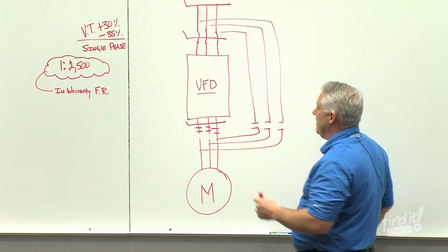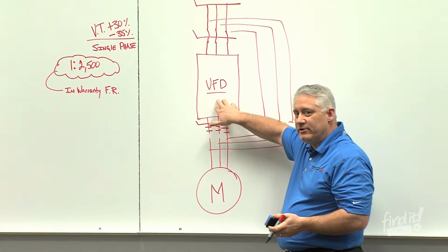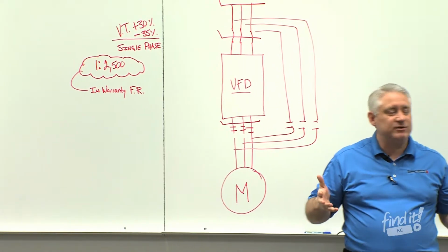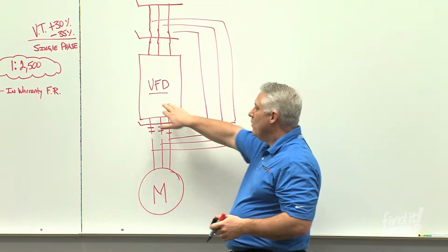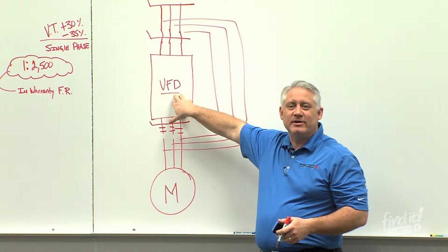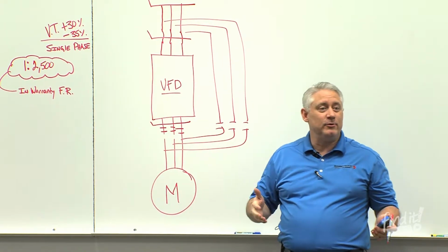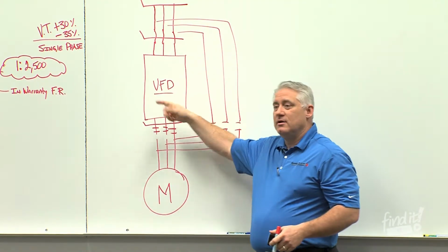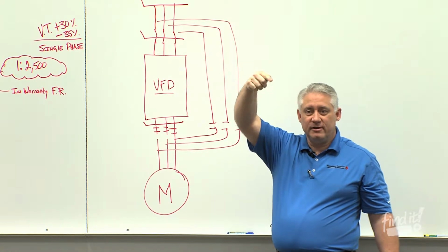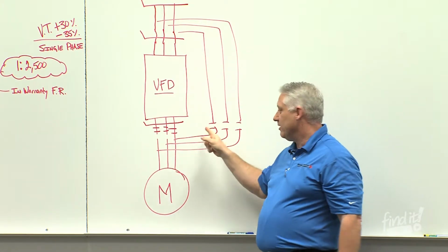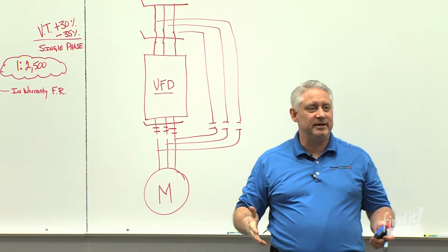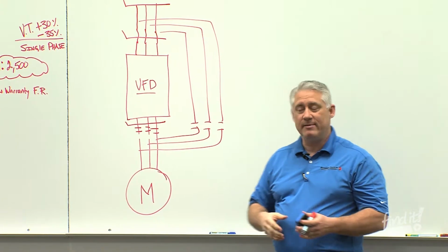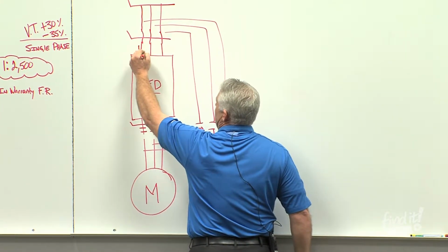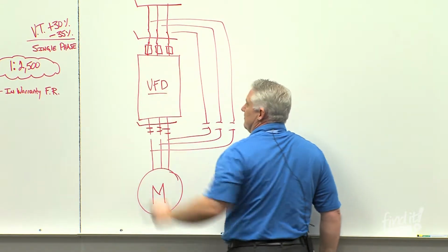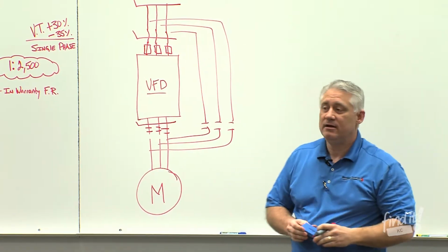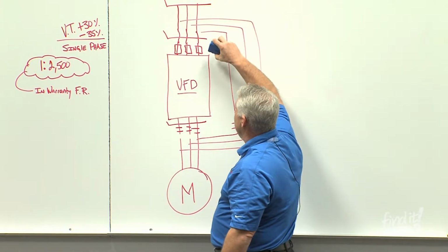So it went from a three-contactor to a two-contactor. The other thing that happened is when there was a critical failure in the VFD, a capacitor failure, just something critical internal to the drive, what would happen? Where would we clear fusing? It would clear it at the branch circuit device. That might be in another room, another building. So now the drive fails, we clear the switchgear breaker, and now we've got to find that breaker somewhere in the building in order to go to bypass. Well, that was a problem. If somebody's on an operating room table and we're trying to maintain positive pressure, we want to be able to get to bypass quickly. So what the drive manufacturers have done is they've added fast-acting drive isolation fuses ahead of the VFD. And their main purpose is to clear in the event that there's a critical drive fault.